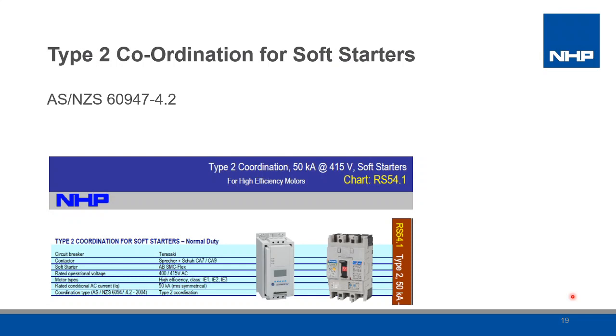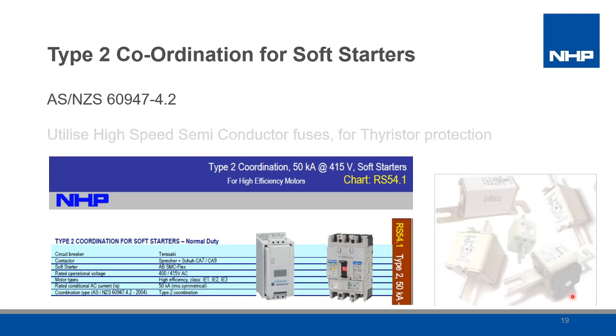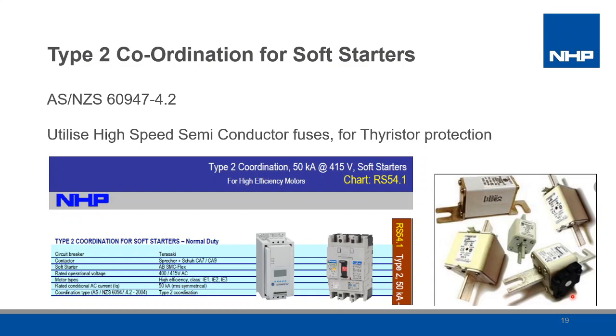However, the testing for soft starter Type 2 coordination is from AS/NZS 60947.4.2 and does have variations from the contactor starter testing. The weak point of a soft starter is the thyristors (SCRs), so high-speed semiconductor protection fuses need to be used for short circuit protection. An MCCB or normal fuse will not open quickly enough under a bolted short circuit fault condition to prevent damage to the thyristors.